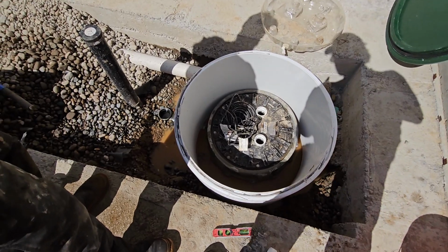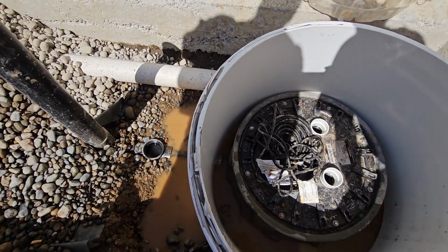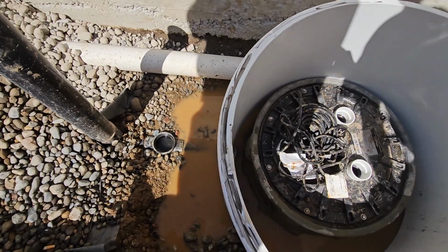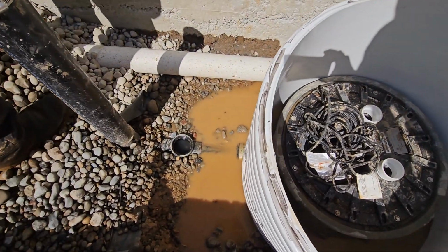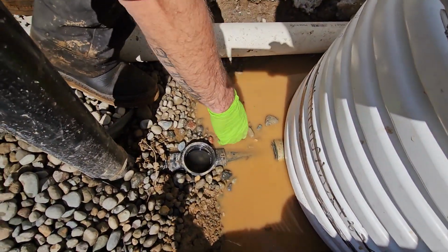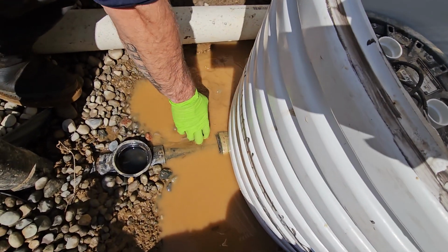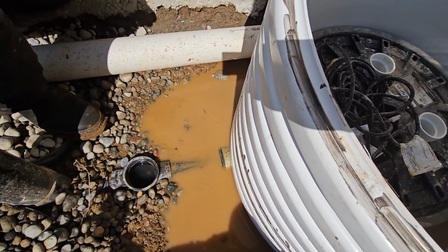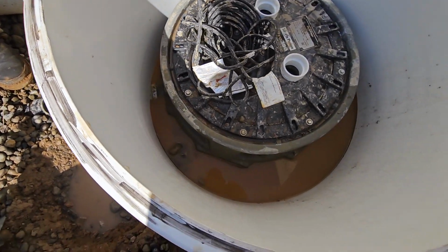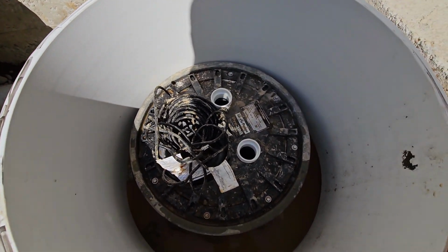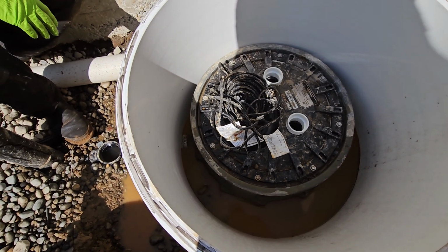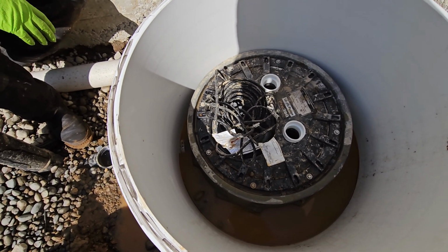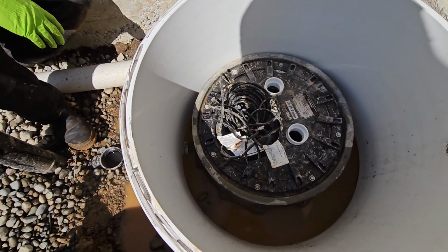So right now, that 300 pounds of buoyancy force is going to put stress on our piping coming into the vessel. That's what's going to take the stress right there, and it's going to try to shear off, and it's going to be a big problem. So to eliminate that, we're going to have them pour that concrete all around here, lock that sucker in there, so the concrete is going to take that force for us and never let that basin pop out of the ground. Okay.